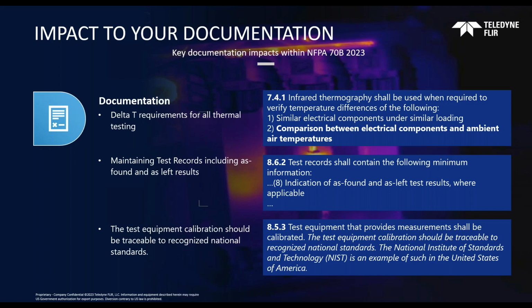Shifting into the documentation side, the worst part of everything is documentation, right? Understanding a little more detail on the delta T requirements, we talk about the two comparisons between the electrical components and ambient air temperatures. The loading piece is very important, but being able to document those things so that as an organization you can over time determine, based on similar load, are we having any changes in our temperatures. There are NETA standards that get to specific actions and activities that should be taken, but we need to make sure we're documenting these things in the most efficient way and maintain those records.